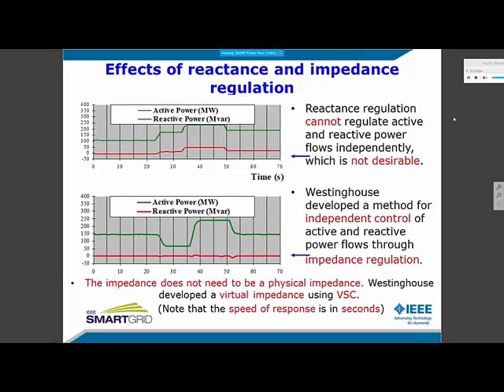Now, here is the result from the 1998 demonstration of the project. We just used the series-connected inverter in the top figure to emulate a reactance. Both P and Q flows either increase or decrease. So the line is never optimized to carry the highest amount of P and the lowest amount of Q. However, an impedance regulation is the better solution. This impedance regulation does not need to be a physical impedance regulation. The virtual impedance is sufficient.